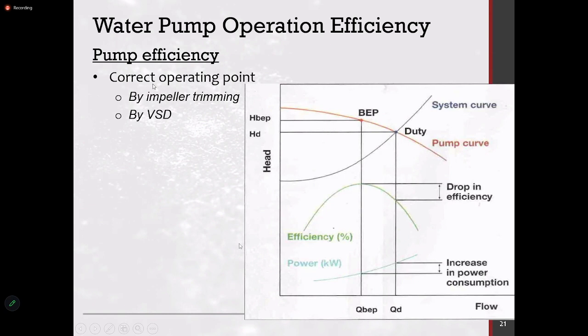Since it is that difficult to select the correct pump curve and you don't get all pump curves for your system requirements, you have to select one curve which is operating closer to the best efficiency point. You do different modifications to the pump to ensure you come closer to this point, which is mainly discussed under impeller trimming and VSD.